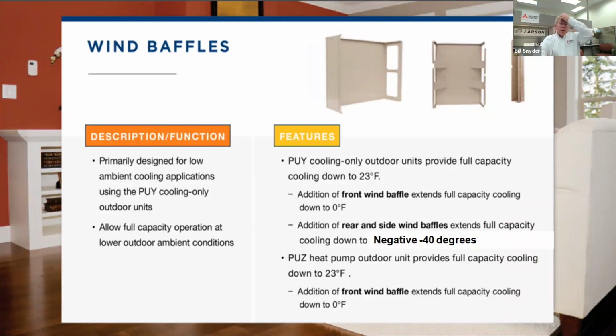Here's the baffles I was talking about, the wind baffles. There's the front, rear, and side wind baffles, and it'll give you a -40 for cooling only units. It's 23 degrees without the wind baffle. With only the front wind baffle, 0, and if you put all 3, you get -40. That's for the cooling only. The heat pumps are 23 degrees cooling, and if you put a front wind baffle on, it will cool down to 0. But if you're selling a heat pump, you probably don't need cooling. You're going to need some heat, and you probably don't need to cool down in those low ambient conditions anyway.